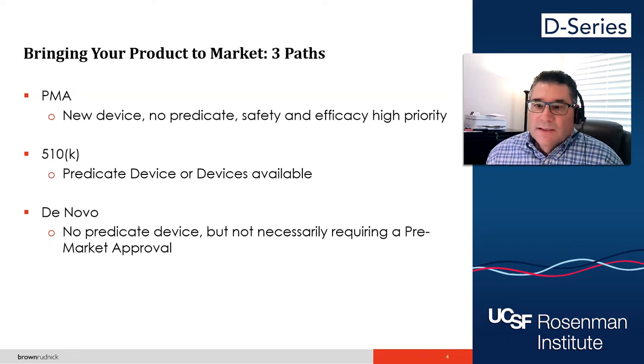The next one is the 510K, and that has something called a predicate device. So if you create a particular heart monitor and it works on the same engineering principle as another heart monitor, even though it enhances it and does it better, then you are able to use the other one as a predicate device. By using it as a predicate device, it's a shortcut to your filing and approval.